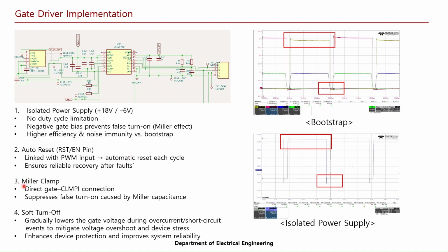The Miller clamp connected directly to the gate suppresses undesired turn-on, and the soft turn-off function gradually lowers gate voltage during short circuit or overcurrent, reducing voltage overshoot and device stress, enhancing system reliability. As shown in the right photo, the bootstrap voltage dropped unstably, whereas the isolated power supply maintained stable plus 18 volt minus 6 volt operation.